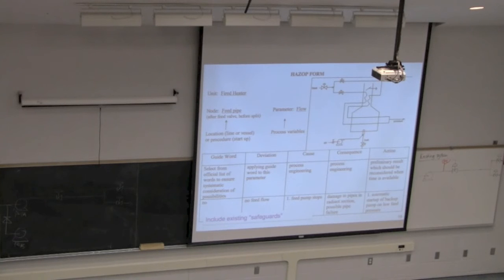Okay, so maybe this is where PNIDs and these decisions are tough, right? Because we want to also have a valve here so we can isolate the pump later on for maintenance. We also don't want a valve here so that we don't have Three Mile Island reoccurring, when valves were shut that weren't supposed to be shut. Okay, so probably no valve. Given that this is a backup pump, it's not intended to be used under normal situations. So no valve for that reason, so that it is going to be available to us.